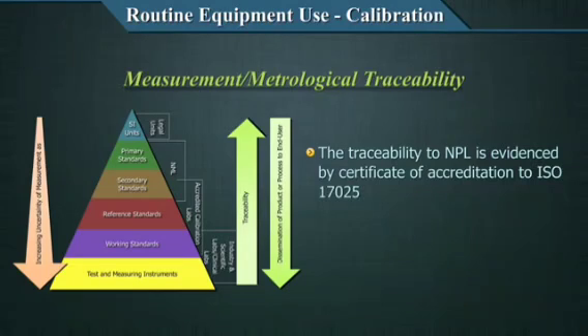The reference material you use in your lab, or those with which external agencies calibrate your equipment, need to demonstrate this kind of traceability to ISO 17025. That is generally given in your calibration certificate. We'll show you an example later. To reiterate, as you see here, there is a dissemination of material in a traceable way, but with a certain level of increasing uncertainty. That was just a reiteration of what I said earlier. I hope that concept is fairly clear to you.